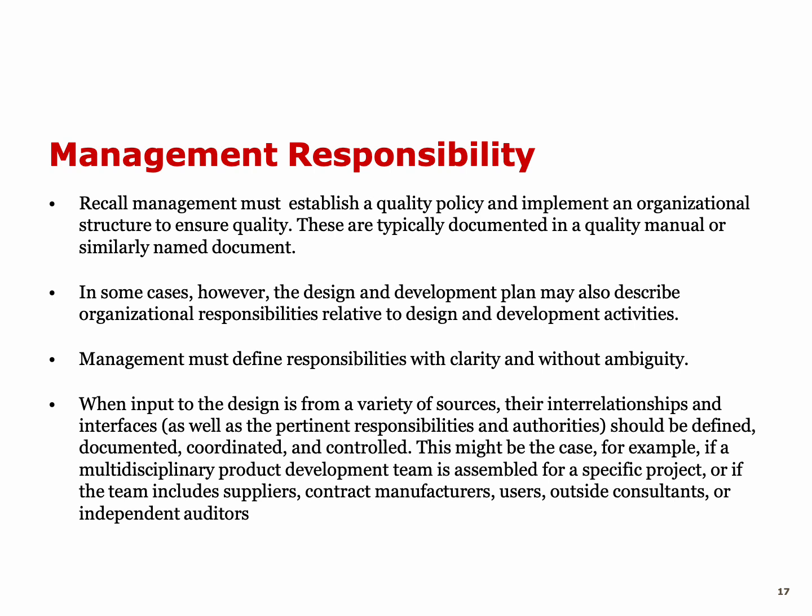And when, again, input to the design is from a variety of sources, their interrelationships and interfaces should be defined, documented, coordinated, and controlled. This might be the case, for example, if a multidisciplinary product development team is assembled for a specific project, or if the team includes suppliers, contract manufacturers, users, outside consultants, or independent auditors.